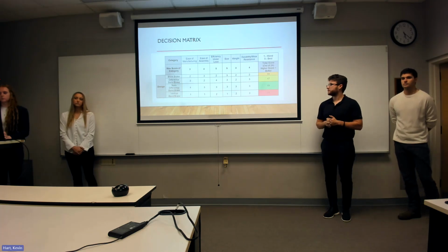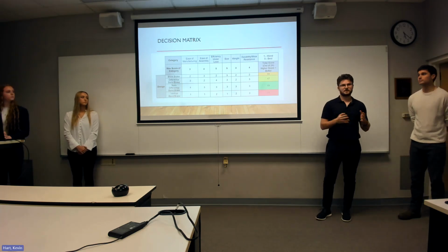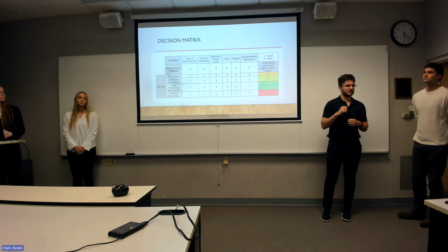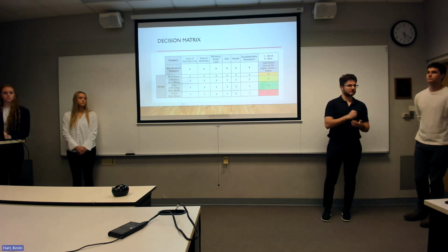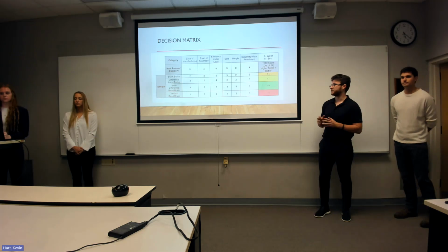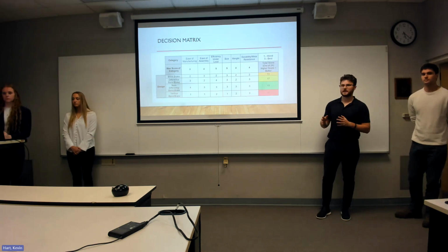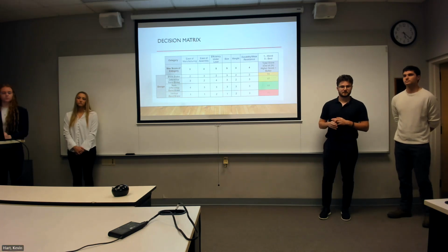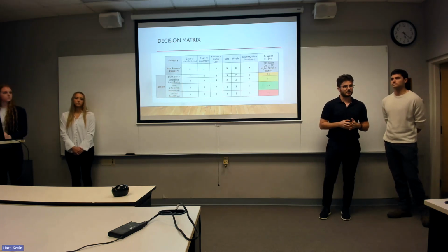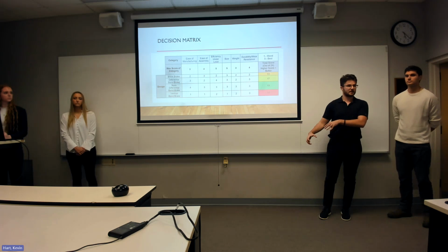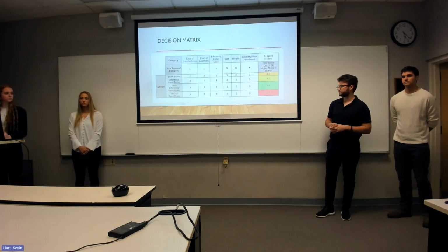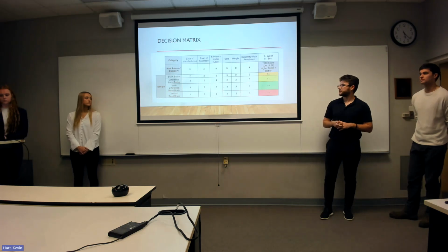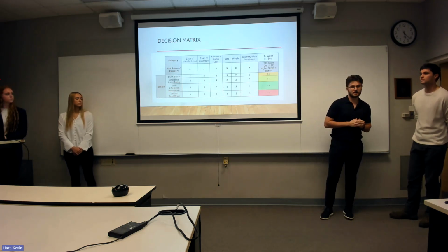The two most important categories that we discussed as a group were the efficiency under load, basically turning that actuation force into stopping the drum from rotating so that the ankle would be able to lock, how efficient that was, and the size, because as you can imagine, the patients that would be wearing this orthotic already have trouble walking, so the last thing that they need is a huge brake on their ankle that makes it even more difficult. So as you can see here, the two best designs that we determined were the differential and the non-differential band brakes.